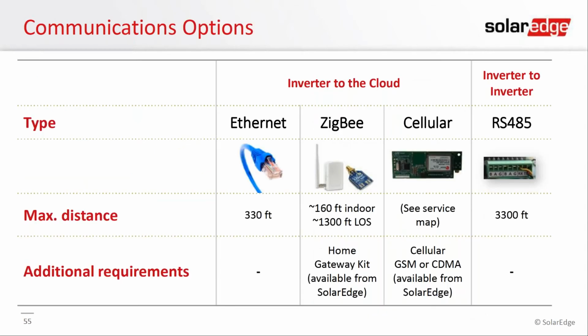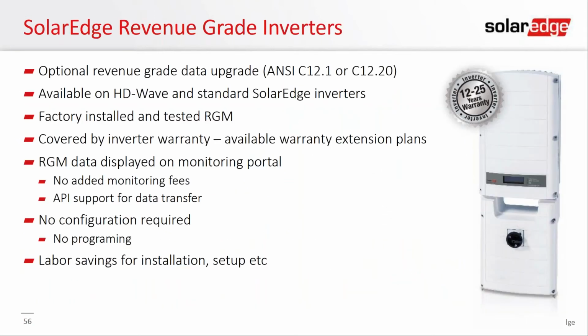So communication options, we've always allowed you to do Ethernet or Zigbee or cellular. Coming by default in StorEdge, communication is so important. Coming by default, we are installing a GSM cellular modem. So we're just going to say, okay, here's the modem, factory installed. All you've got to do is turn on the inverter. Revenue grade options are also available. So if you are in a place that has SREC and you need some revenue grade metering, of course that option is available. It's factory installed, tested. It's a fantastic product, covered by the warranty.